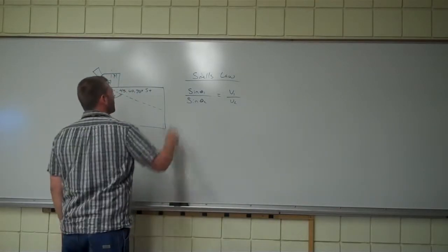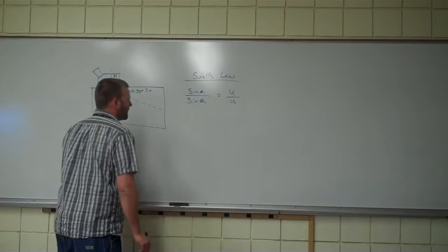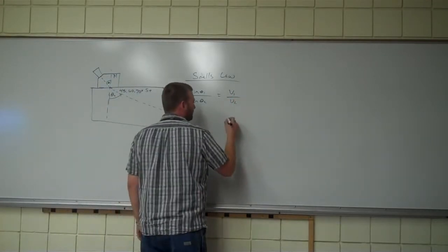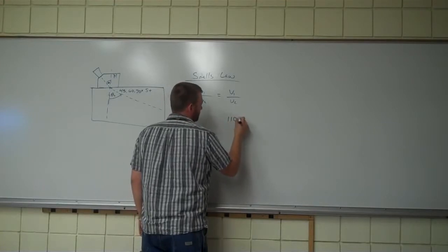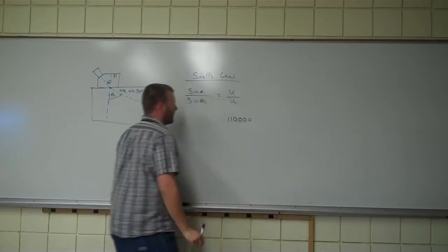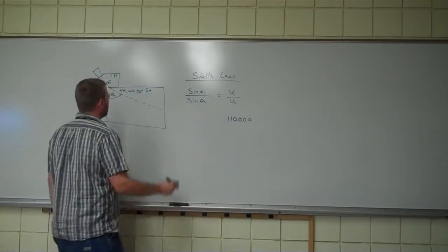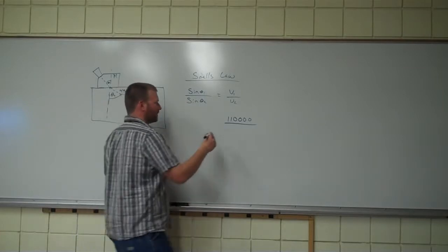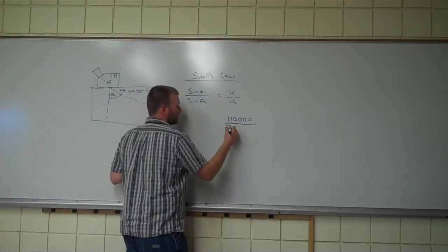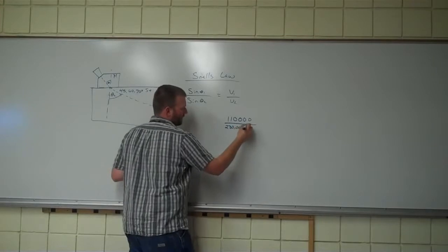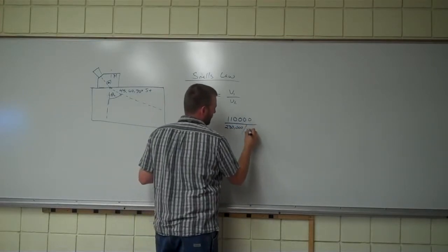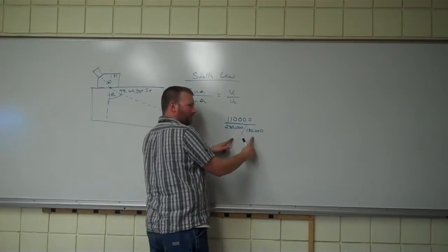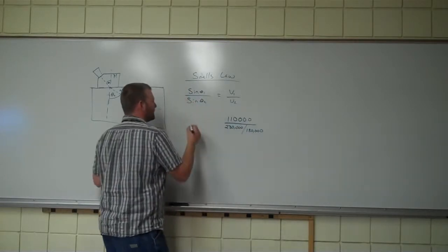So, let's just for kicks and grins plug some numbers in and see what we come up with. Let's say our first material is plexiglass, so I'm going to plug in the velocity of plexiglass, about 110,000 inches per second. And I'm going to plug in two velocities: first the longitudinal velocity of steel, and the shear wave velocity of steel. Now don't get this confused. I'm actually writing two different problems here, but I'm just condensing space.